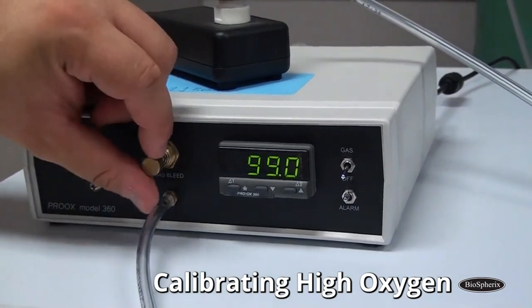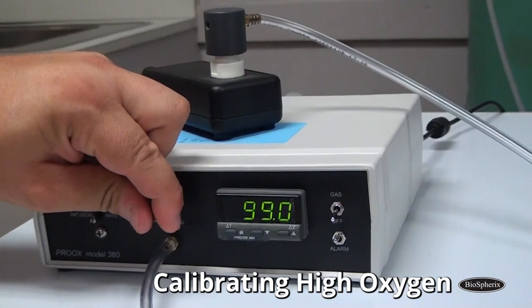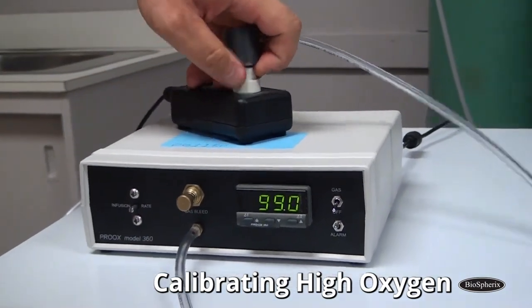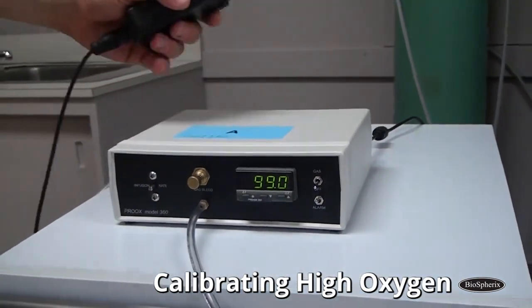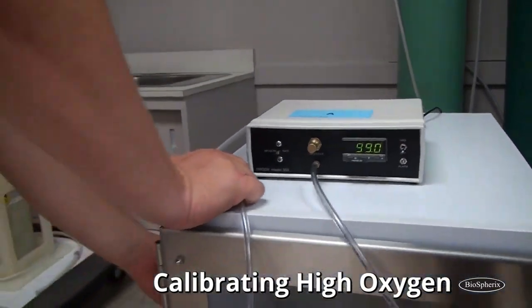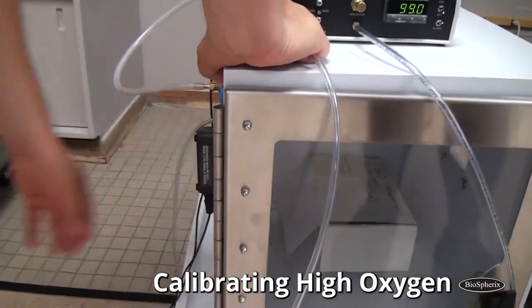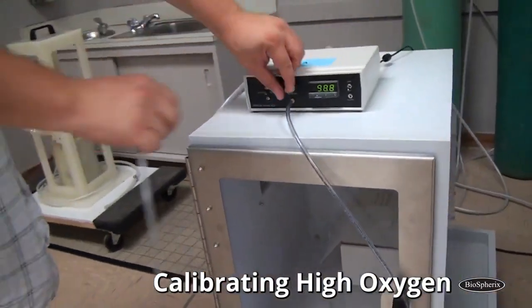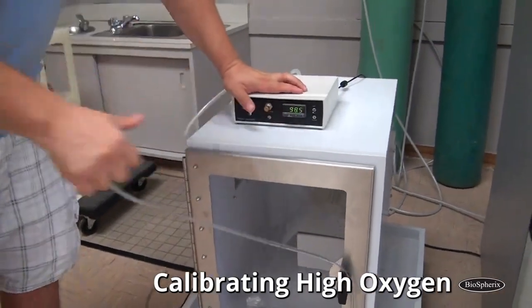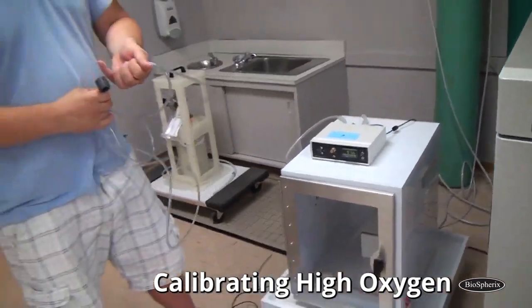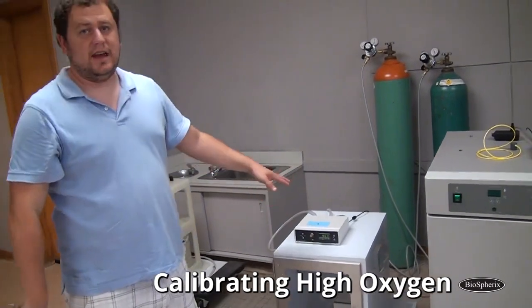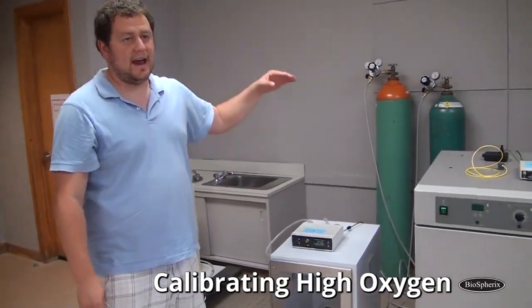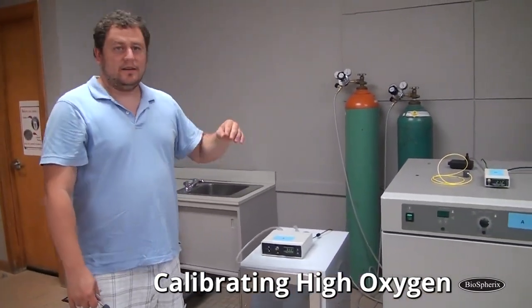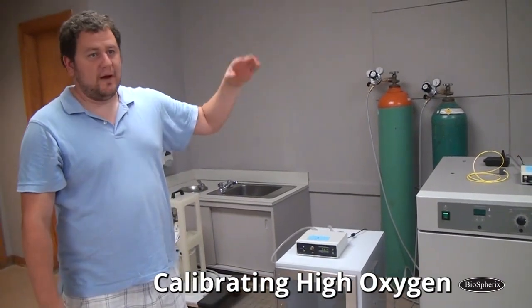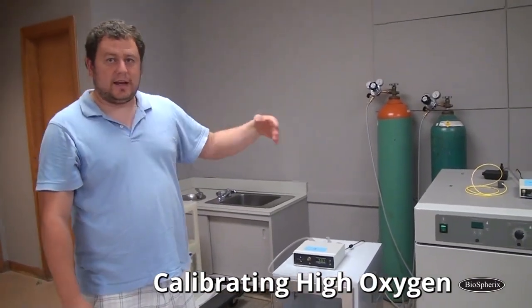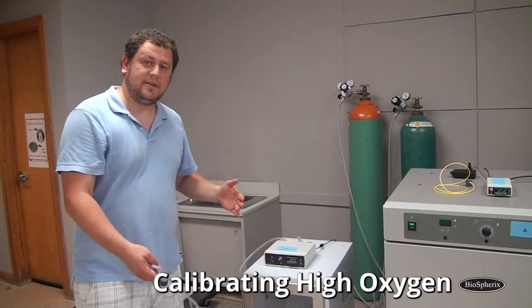I'm going to shut my gas off. Take my calibration chamber off. Return my sensor. And I'm all set to start using again. I wanted you to get a good idea of how it works at the high oxygen. As you can see, there's a little bit of back and forth. It's not quite as quick and as accurate as the other method.